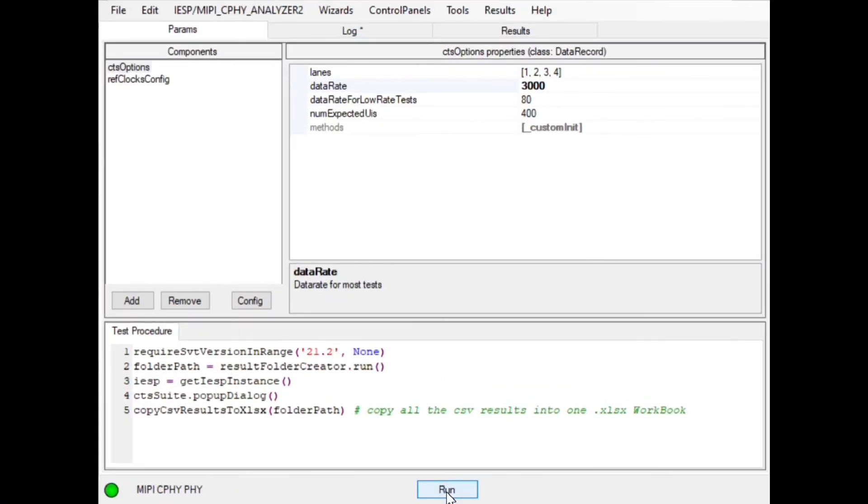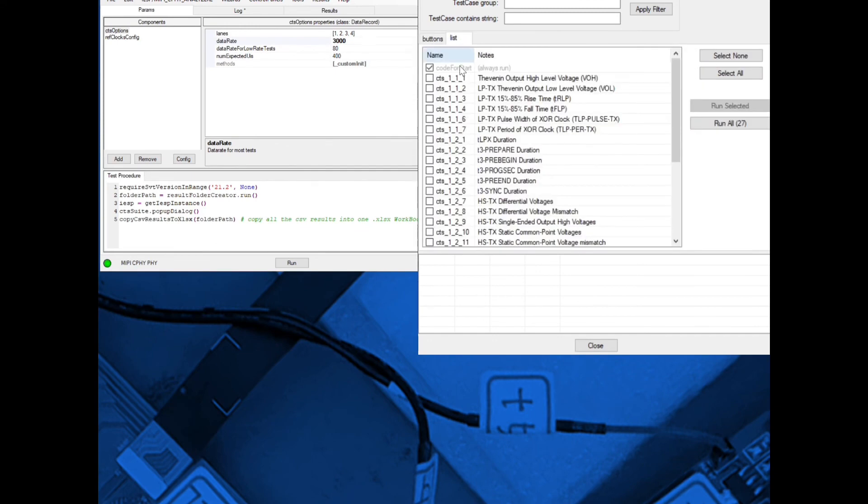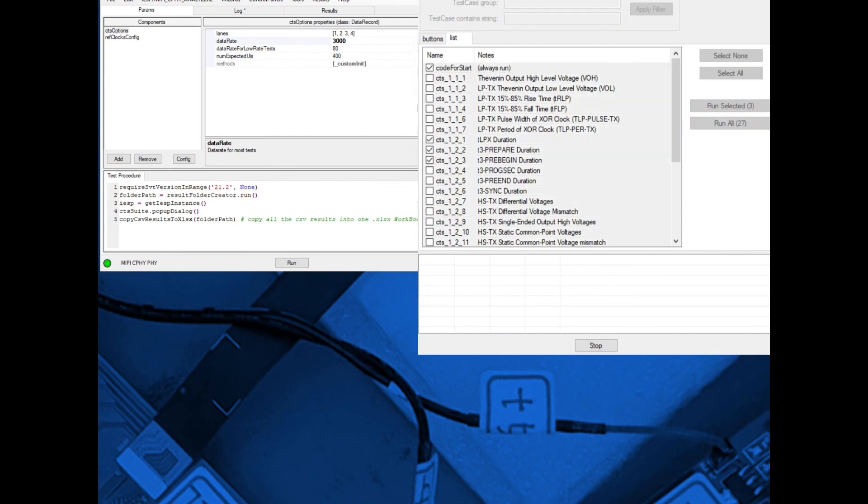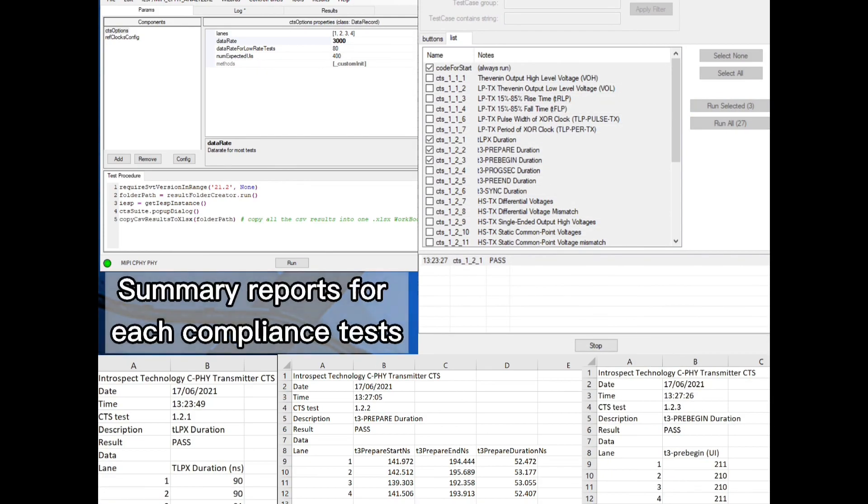The SV5C MIPI analyzer supports C-PHY 2.0 and D-PHY 3.0 transmitter CTS testing. The CTS software interface provides convenient methods for selecting and executing tests, generating easy-to-read summaries of pass-fail compliance test results, and presenting clear individual summary reports for each compliance test executed.